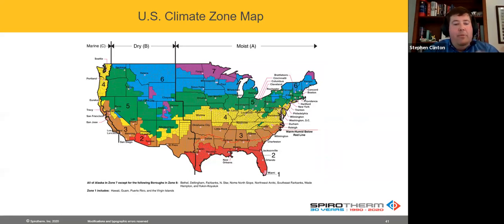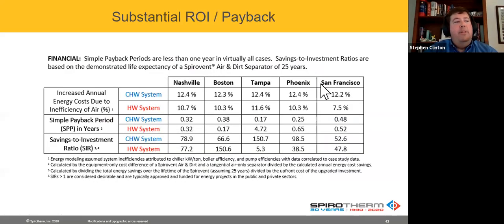Again, we'll be happy to sit down and go through all the data, but this is what we came up with. What we found when we modeled that, going from a system with no air in the system to modeling it to case study, was that you would be paying a penalty of 12%, plus or minus a point or two, on the chilled water side and on the heating hot water side as well. On the simple payback, that led to 2 months of discussion. This whole thing took about 10 months.